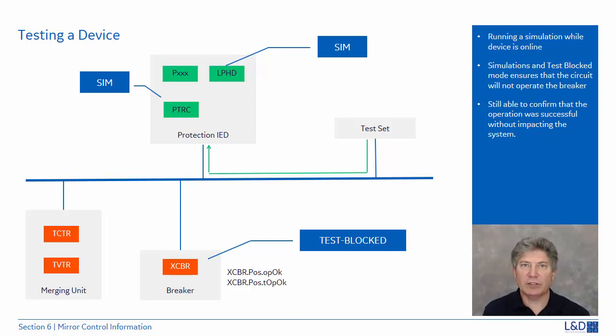The protection IED will now receive the sampled values from the test device and will initiate a trip. The trip is sent as a GOOSE message with the quality flag of the trip signal set to test. The XCBR will receive and process that trip. However, no output will be generated since the logical node mode is set to test blocked.